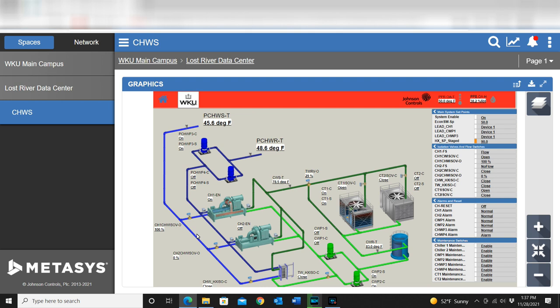If you have any type of alarming on your system, it can flag an alarm if you do not have some type of reporting delay. But again, it's nothing that actually affects the system. Depending on your alarm reporting, it can flag a temporary alarm. In fact, this one would flag one for just a few minutes. Looking at some of the trends, it would go into alarm for just a very short period of time before returning to normal, where that temperature has dropped. So that's a change that we had to make within our system recently.